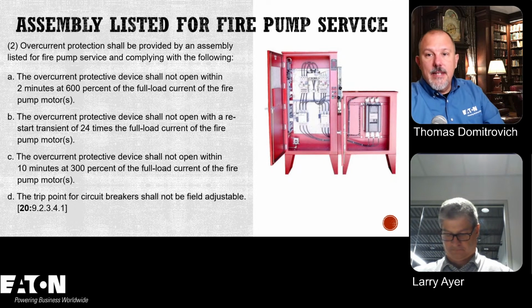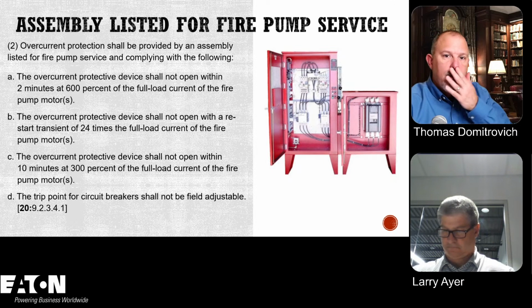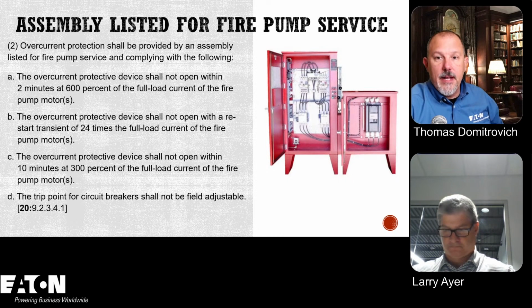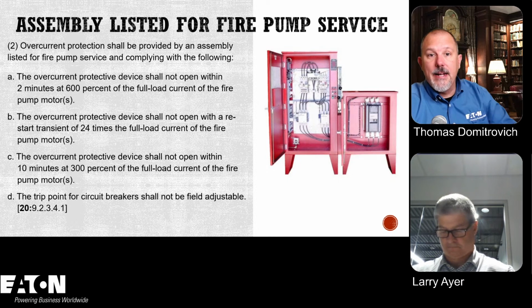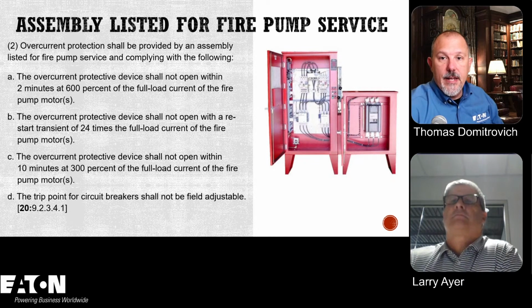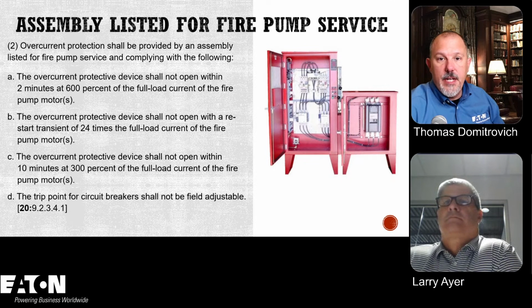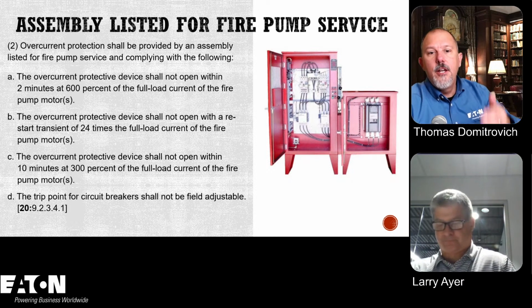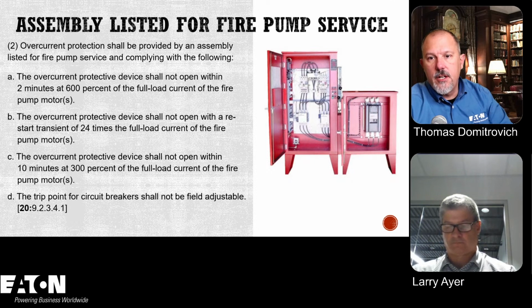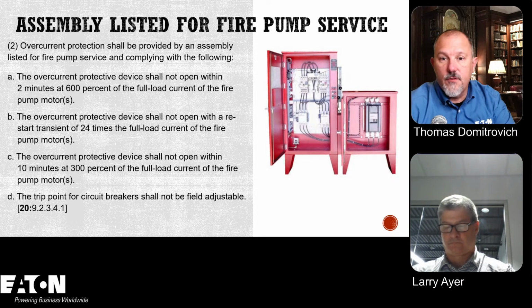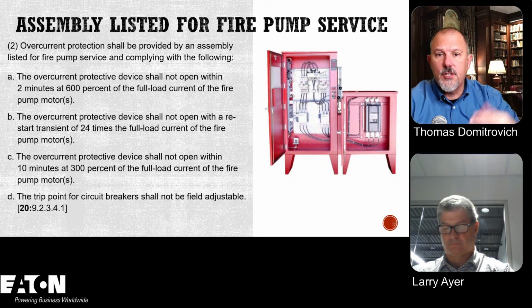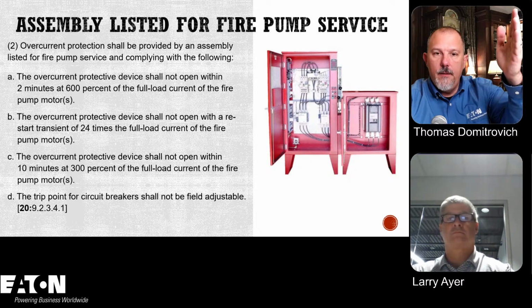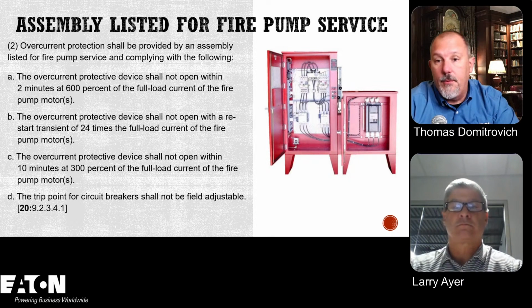Okay, so assemblies listed for fire pump services. This is getting into what is provided by an assembly listed for fire pump service and complying with your A through D. And this is right out of the NEC, because there's a reference to NFPA 20 there. And this is your 600%. Your overcurrent protective device shall not open with restart transients of 24 times the full load, and the overcurrent device shall not open within 10 minutes at 300%. So this is giving you how to compare that trip curve with these data points, right?